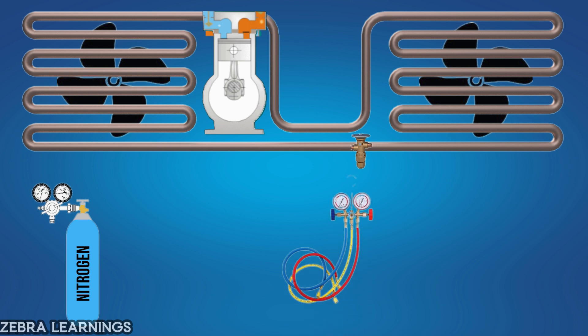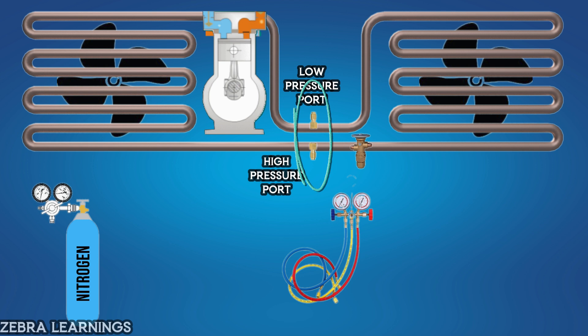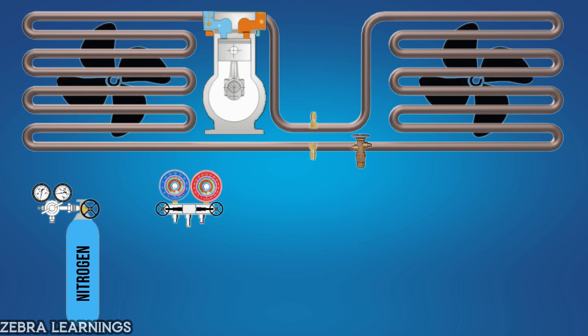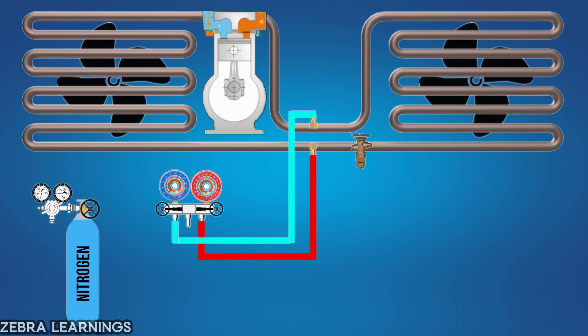If the outdoor unit has connecting ports on both the low pressure and high pressure lines, connect the blue hose to the low pressure line and the red hose to the high pressure line. However, if there is only a connecting port on the low pressure line, then connect only the blue hose to the low pressure line. After connecting the blue and red hoses, connect the yellow hose to the outlet of the regulator.